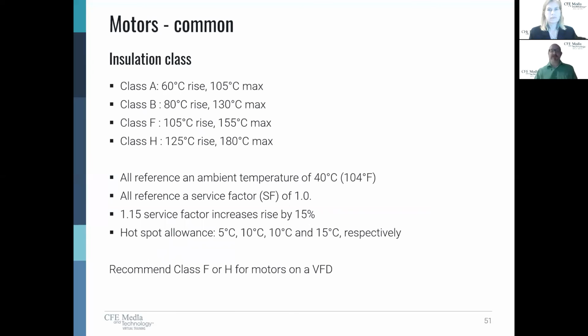We're also going to consider service factor. So if I have a higher service factor, then I'm allowing for a hotter hot spot. And what that means is that just because we have heat being generated by current doesn't mean it's the same everywhere. We expect that at certain parts of the motor, it's actually going to be a little bit hotter than in other spots. So as we look at our hotspot allowances and based on our classes, we can increase that with our service factor. So really the takeaway here is that you're always going to take your environment into consideration for heat, for temperature, humidity, whether it's fans, whether it's motors, whether it's pumps, whether it's VFDs. We're always going to take our environment into consideration so that engineers are looking at projects holistically.